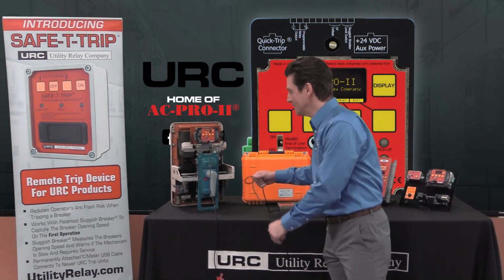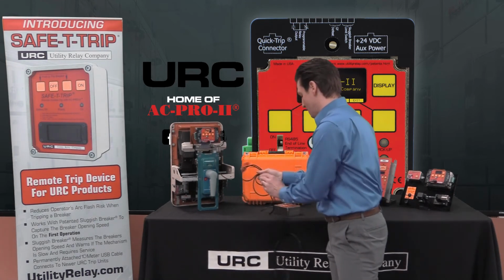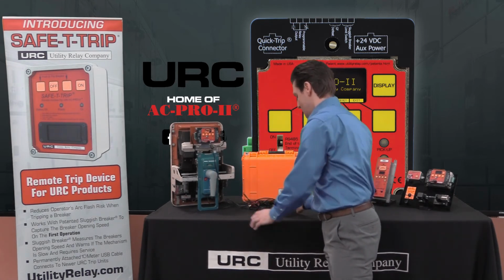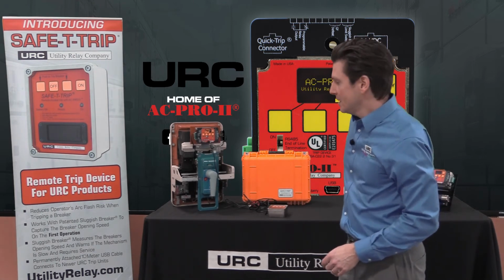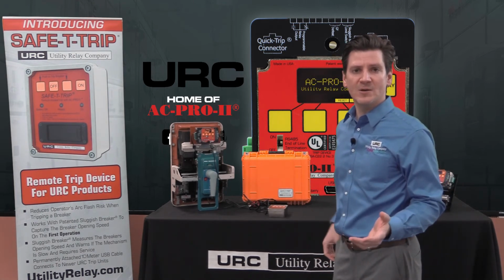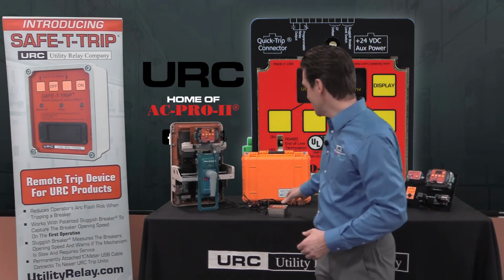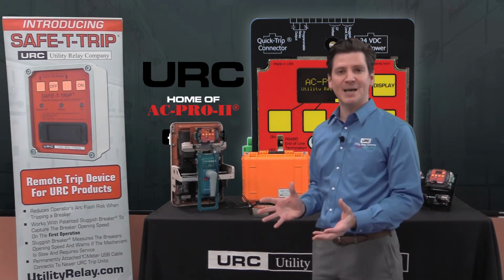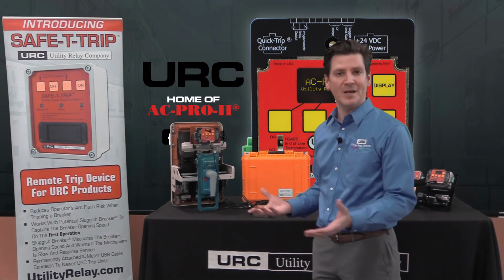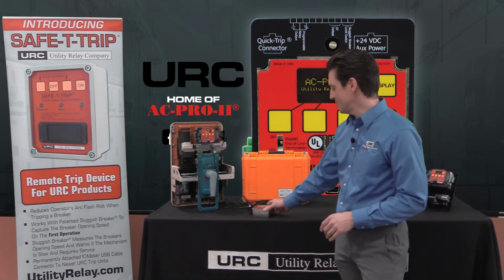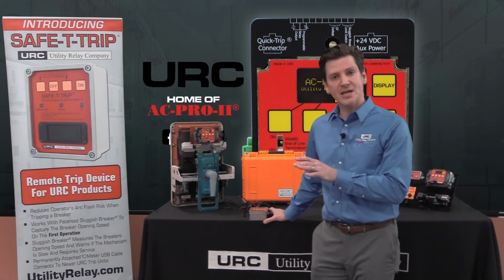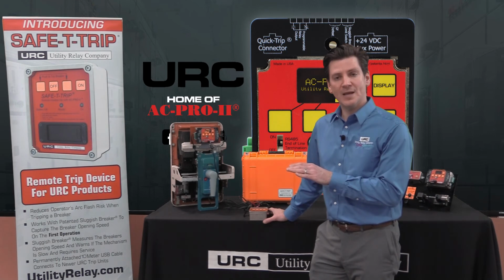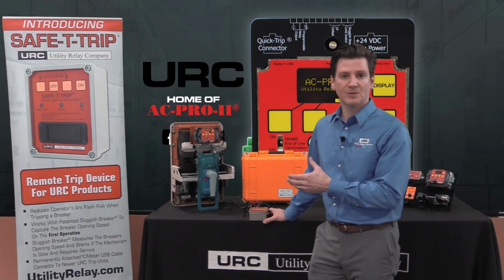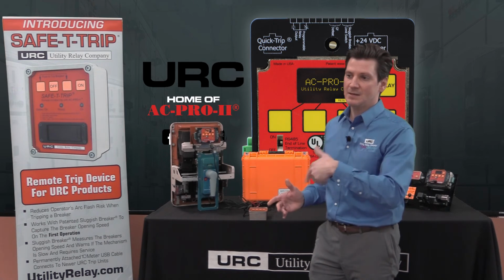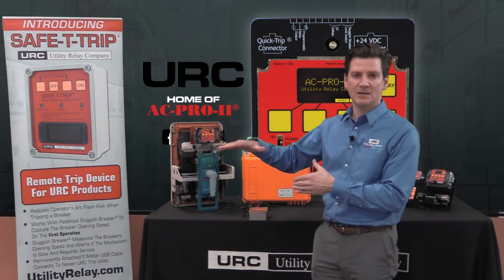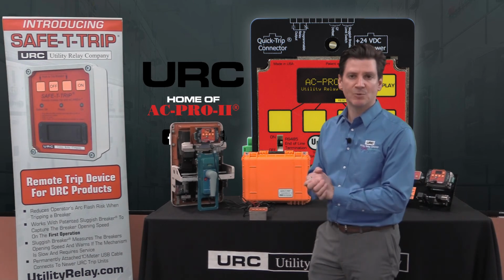In addition to opening the breaker, as I just demonstrated, the Safe-T-Trip works with our patented sluggish breaker detection technology. We'll talk about that in more detail in another segment, but the sluggish breaker feature essentially measures the opening time of your circuit breaker to make sure that it's opening as quickly as it should. The Safe-T-Trip initiates that circuit breaker opening, and you can measure the critical first operation of the breaker. That's a data input that you need to set the sluggish breaker threshold and make sure it is programmed properly for you.